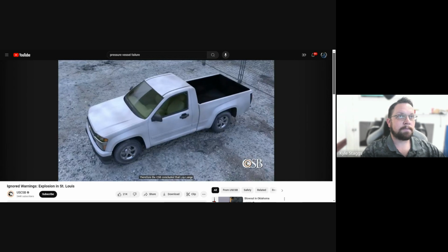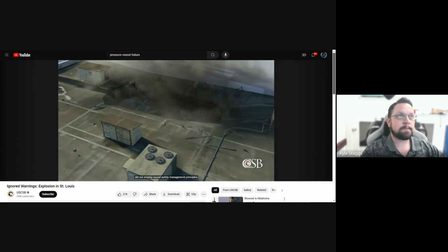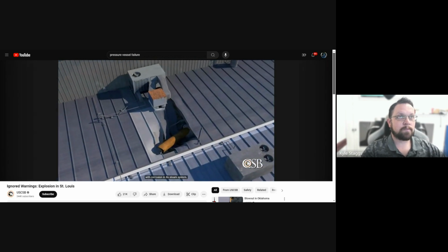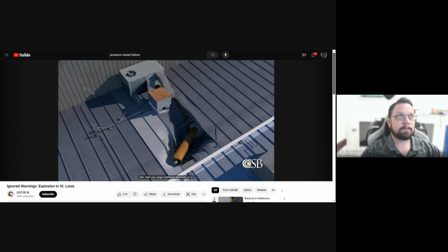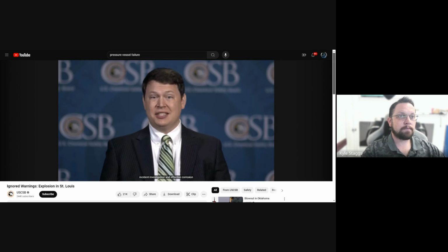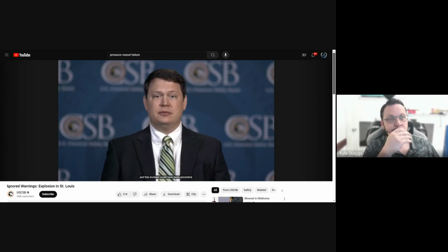Therefore, the CSB concluded that Loy Lang did not employ sound safety management principles in addressing the risks associated with corrosion in its steam system. Had Loy Lang instituted elements of an effective safety management system, including mechanical integrity, incident investigation, and effective corrosion prevention programs, the hazard of corrosion could have been mitigated and this incident could have been prevented.